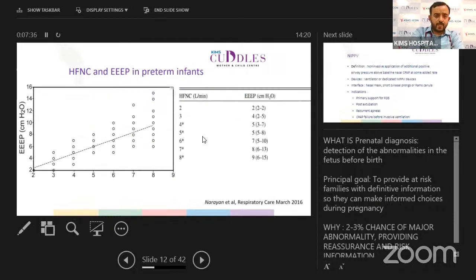This is the graph, the picture that again shows the variability that is seen with increasing flows. As we can see, with flows of around 3 to 4 liters per minute, the end expiratory esophageal pressure varies between 4 to 5 or 4 to 6. But as we go up to 7 to 8 liters per minute flow, the pressures can even go up to 12 to 14 centimeters water. So these unchecked pressures can sometimes cause barotrauma to the lungs and cause air leaks. So one has to be conscious while using higher flow rates of around 7 to 8 liters. This is the table that again shows the range at a flow rate of 8 liters per minute. We can see that the pressure that is generated can vary between 6 to 15 centimeters water.